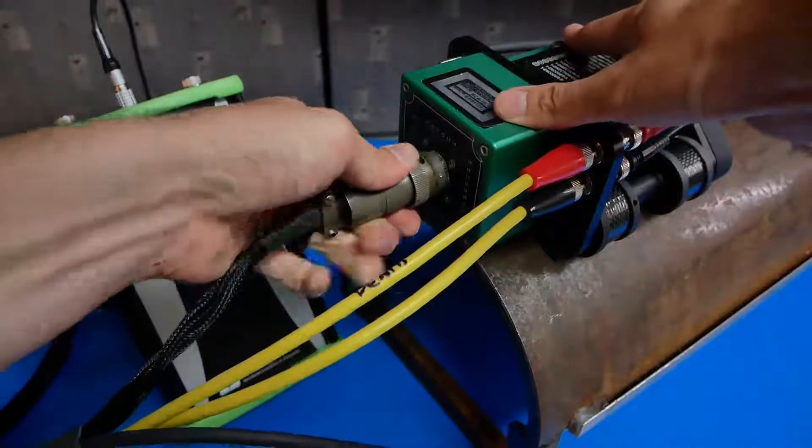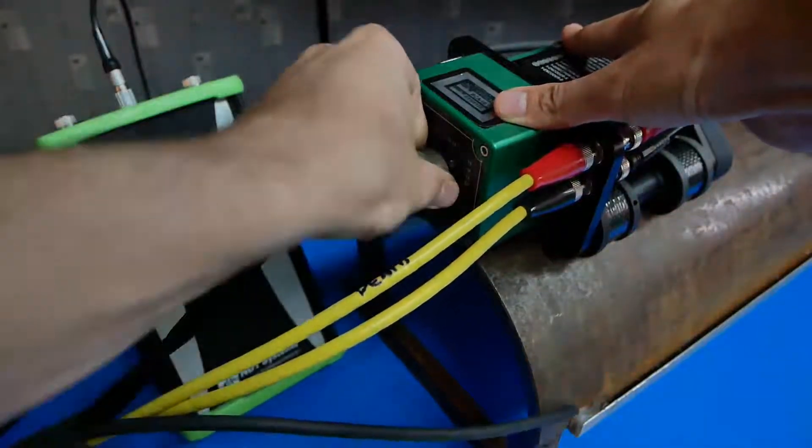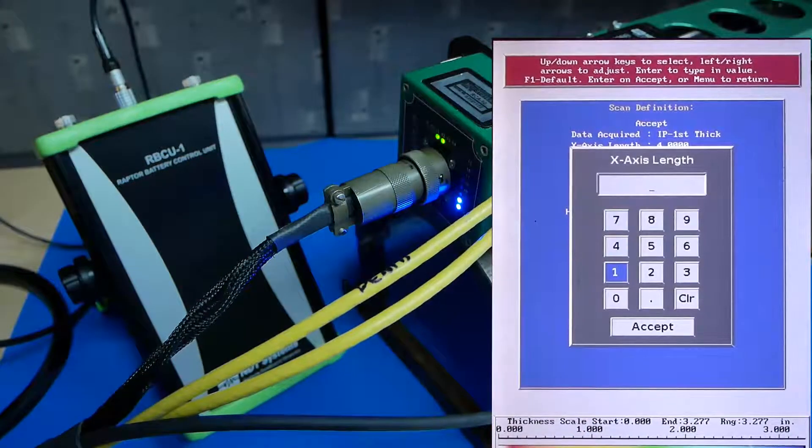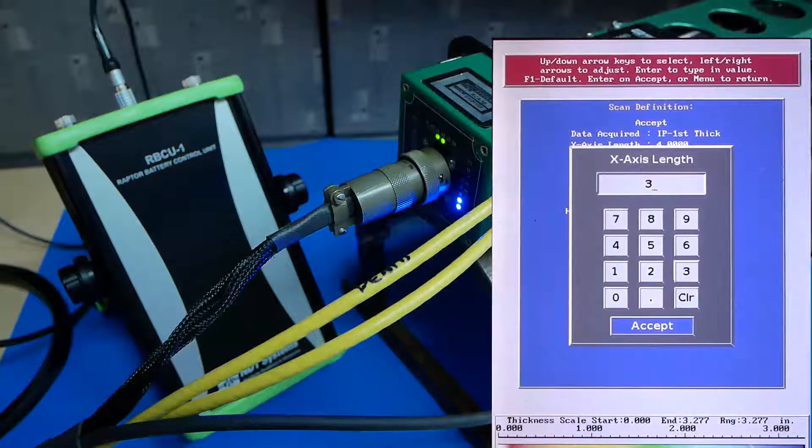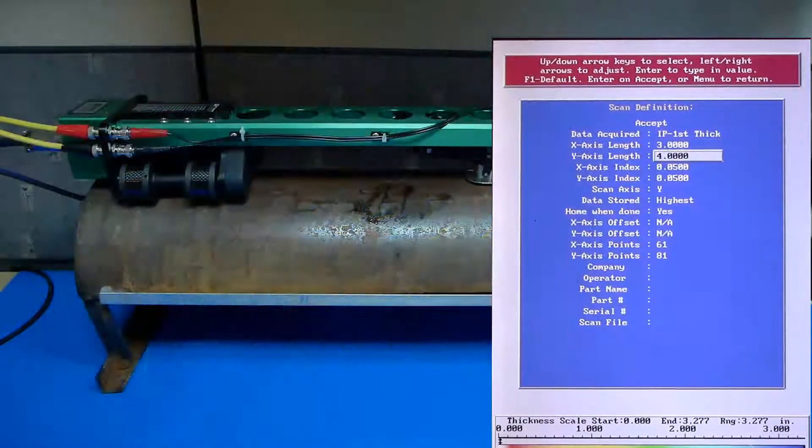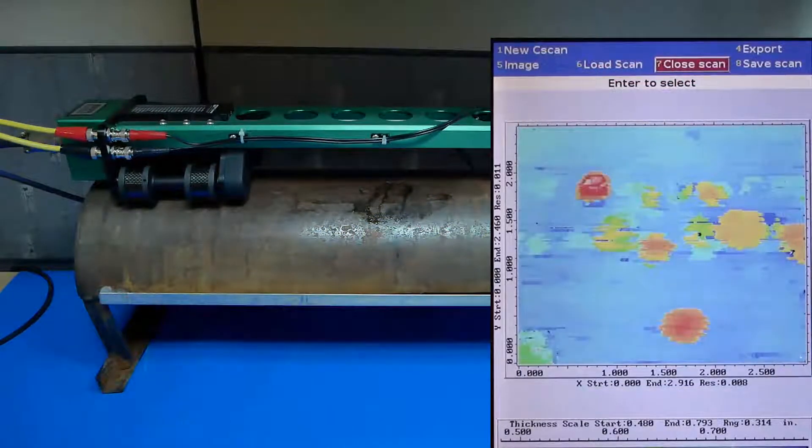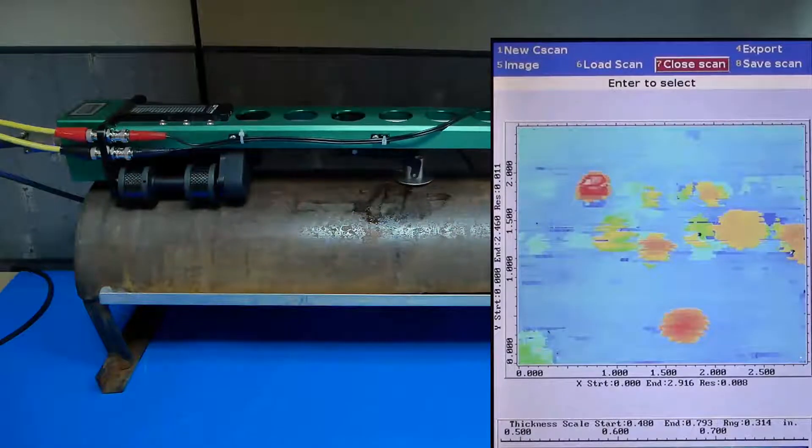Performing a scan is as easy as plugging the Raptor flaw detector into the scanner and inputting the parameters of your scan. As you can see here, setting up the inspection is quick and simple, and you can see the C-scan image being updated live on the screen as the scan is performed.